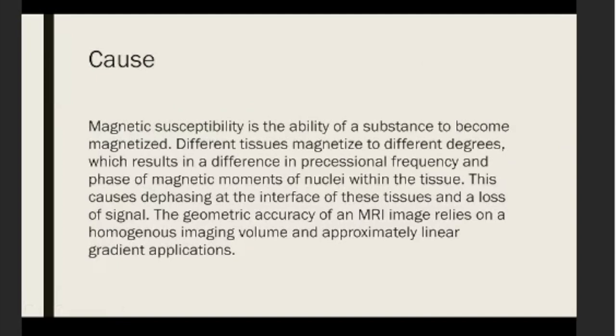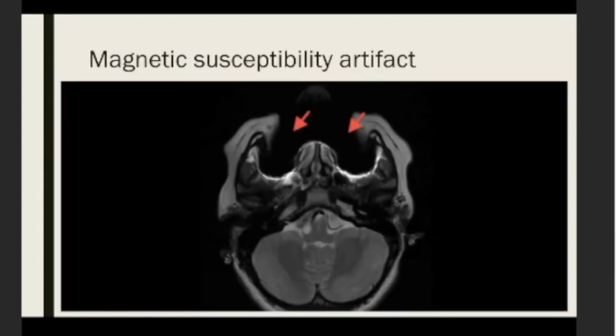The cause of magnetic susceptibility artifact is the ability of a substance to become magnetized. Different tissues magnetize to different degrees, which results in a difference in the frequency and phase of magnetic moments of nuclei within the tissue. This causes dephasing at the tissue interfaces with loss of signal. The geometric accuracy of an MRI image relies on homogenous image volume and approximately linear gradient applications. Here is another example showing magnetic susceptibility artifact in a patient with tooth braces.